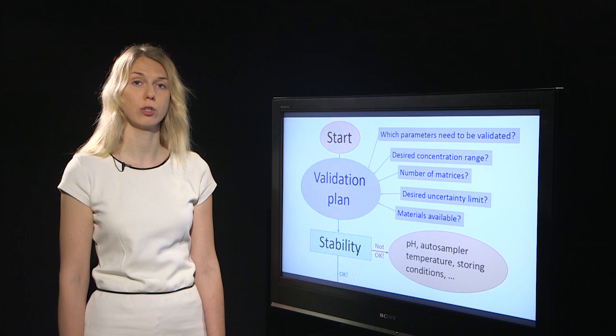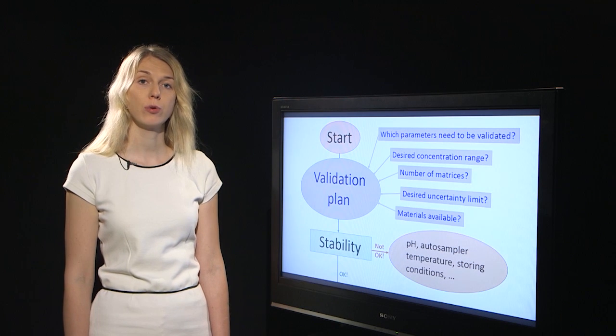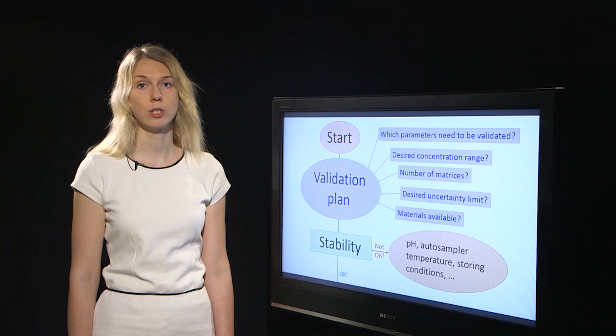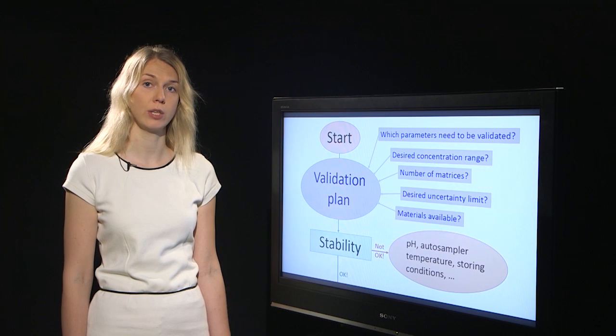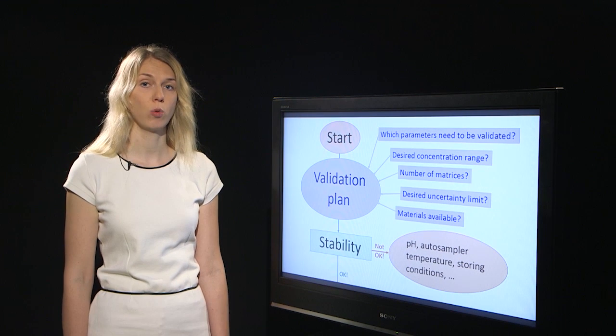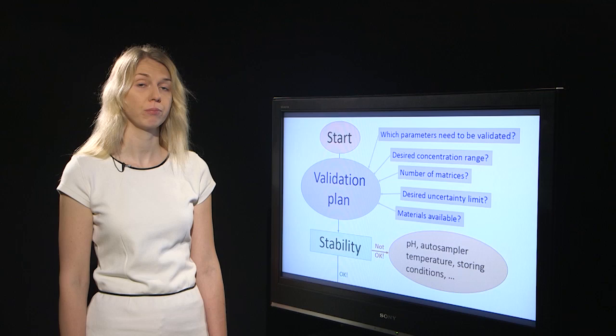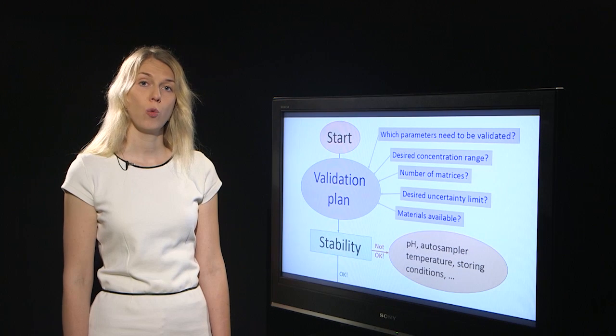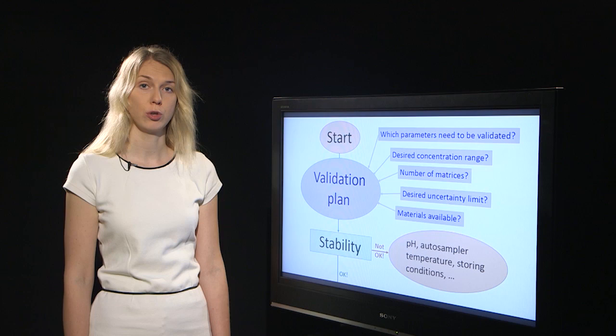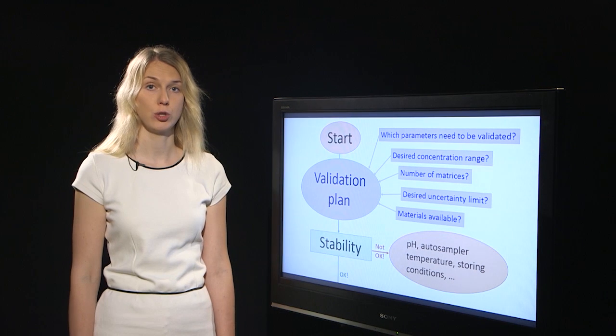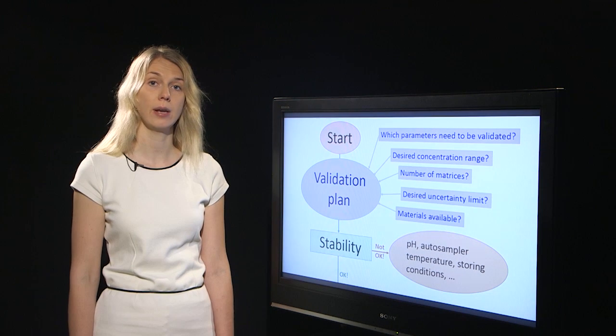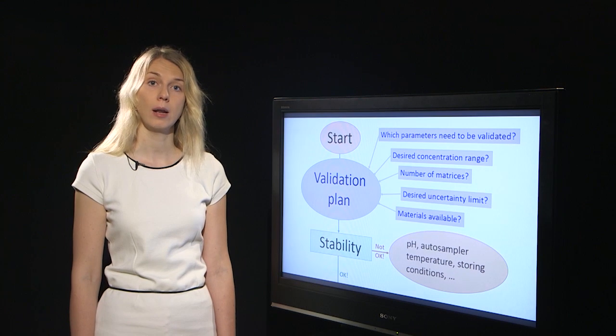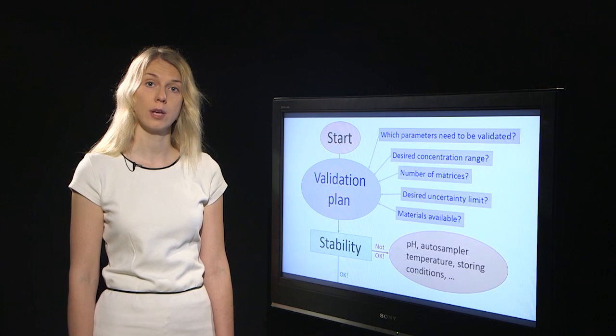You should also consider what requirements are set for your method — what is the precision limit and how low LODs are required, for example. Also it is wise to consider what materials are available to you during validation, for example whether there are any reference materials available for your analyte in your desired matrices.